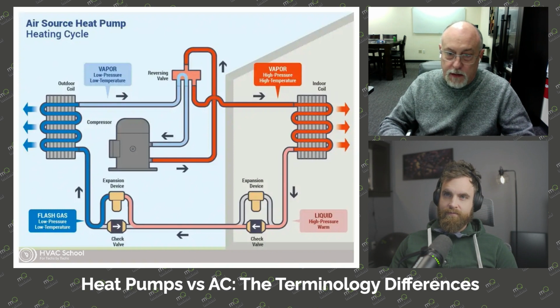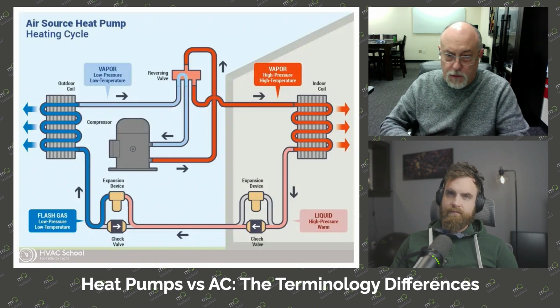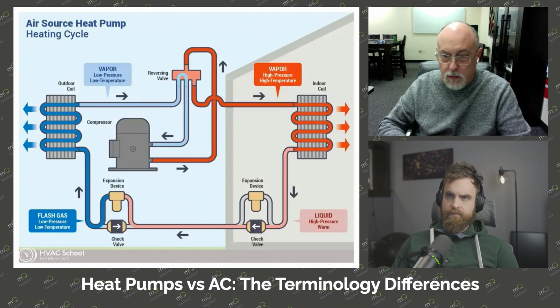The indoor coil can serve two functions. The outdoor coil can serve two functions. Now we have a vapor line because it can be hot vapor or cold vapor. And we have a liquid line, and the liquid can travel in either direction, because it's either traveling into the indoor metering device for cooling or into the outdoor metering device for heating. So now we have two metering devices too, one indoors and one outdoors. Now we have to make sure we have proper evaporator superheat in the cooling mode, and proper superheat entering the compressor in the heating mode, because we don't want to flood our compressor with liquid. So we have two valves that may need adjustment and testing.